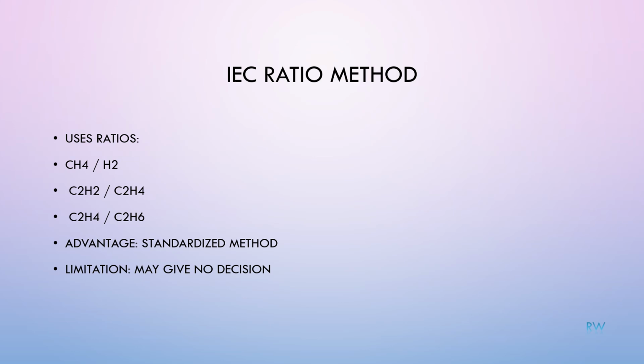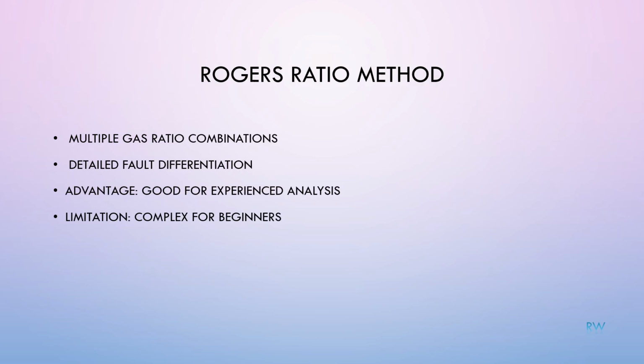The IEC ratio method uses ratios between specific gases instead of absolute values. For example, methane to hydrogen ratio, acetylene to ethylene ratio, and ethylene to ethane ratio. This method reduces dependence on total gas quantity and improves diagnostic clarity. However, sometimes it may produce a no-decision result. The Rogers ratio method is similar to the IEC method but uses additional ratio combinations. It provides more detailed fault classification. It is generally preferred by experienced engineers but may be complex for beginners.